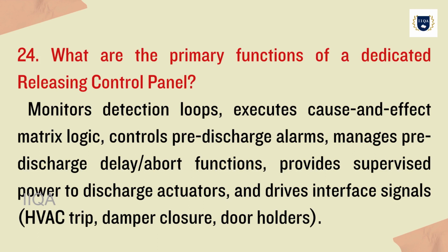24. What are the primary functions of a dedicated releasing control panel? Monitors detection loops, executes cause and effect matrix logic, controls pre-discharge alarms, manages pre-discharge delay and abort functions, provides supervised power to discharge actuators, and drives interface signals: HVAC trip, damper closure, door holders.